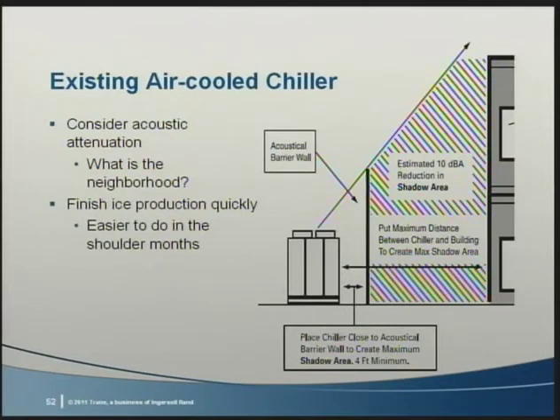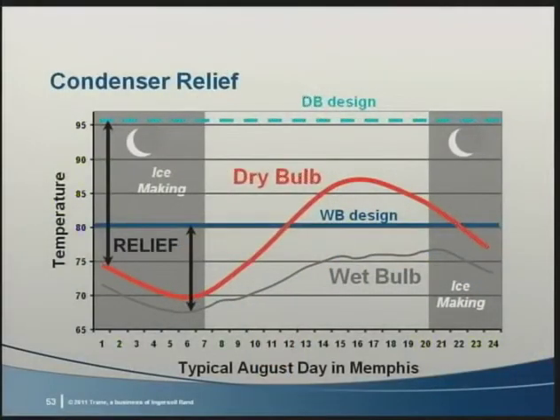Acoustic attenuation could be on the chiller itself, or an acoustic barrier such as a wall between the chiller and the neighbors. But be mindful about where you put any new walls. Too close, and it may cause too much recirculation of condenser air. So why is this a more attractive option for an existing air-cooled chiller and not water-cooled? Here's a popular graphic from a past broadcast. Air-cooled shows a better efficiency benefit from ice storage. This is because during nighttime ice-making mode, the ambient dry bulb drops more significantly than the ambient wet bulb.